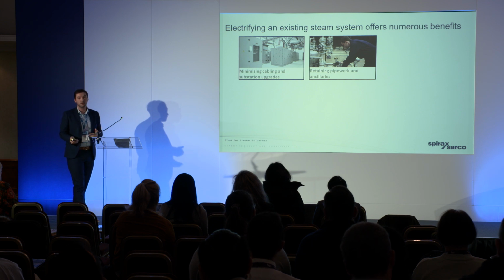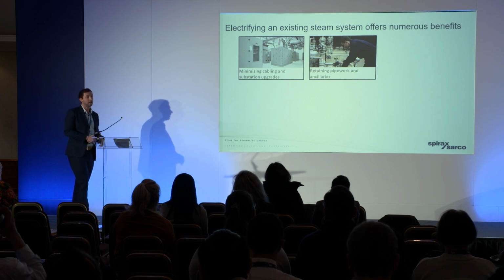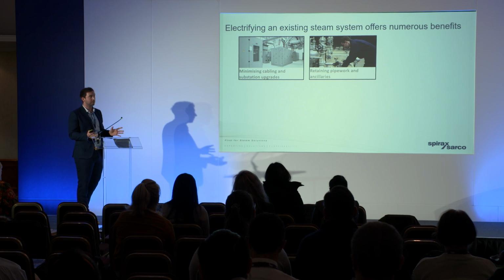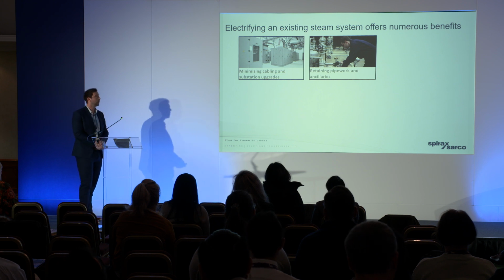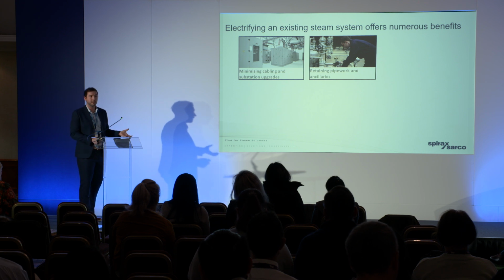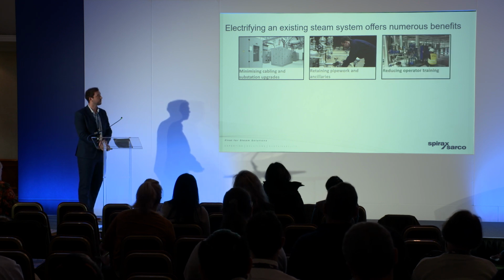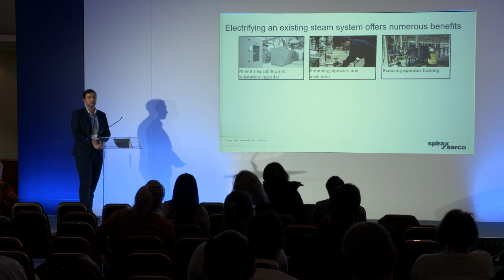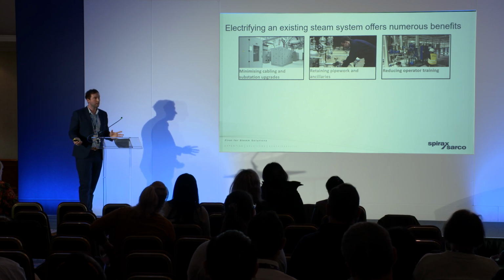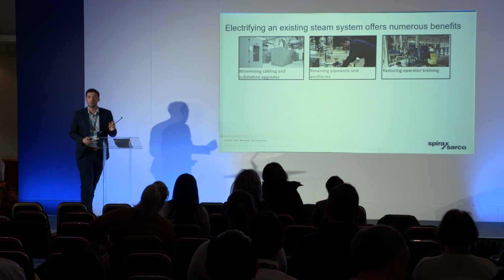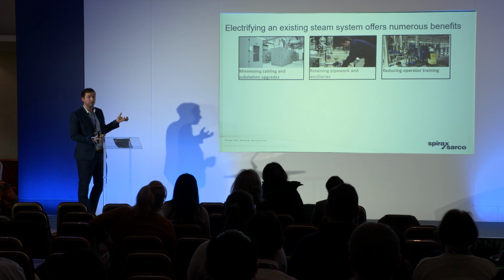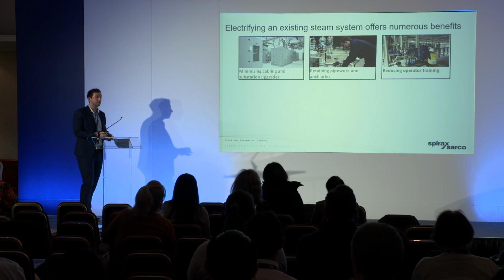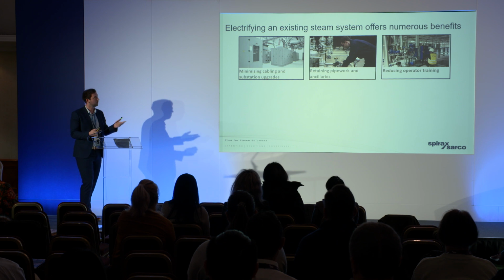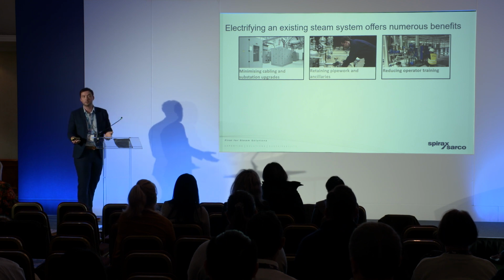We're retaining the pipework, ancillaries, valves, insulation, all the things that are already existing in the hospital, and we're able to retain all of those because it's the same steam going down the pipe. It's just been generated from electricity, not gas. The operators already know how to use all the equipment because it's only a small proportion of the equipment that's changed in the steam generation. We've got the same end-of-use kit, the same distribution system, same valves, same ancillaries, same approach to maintenance.